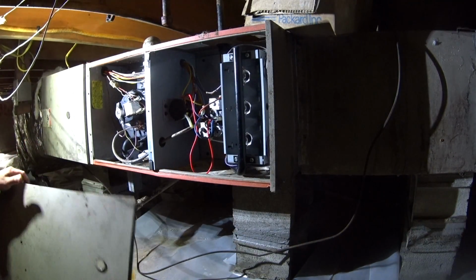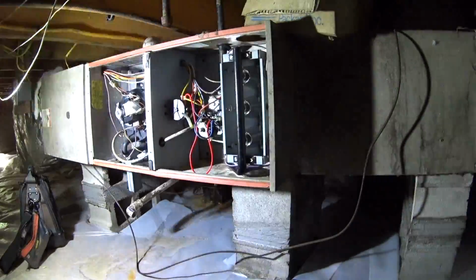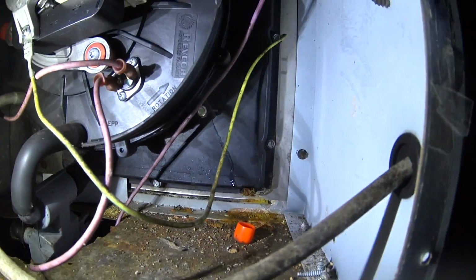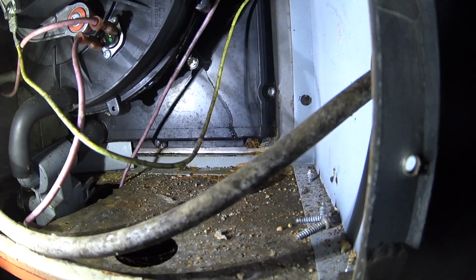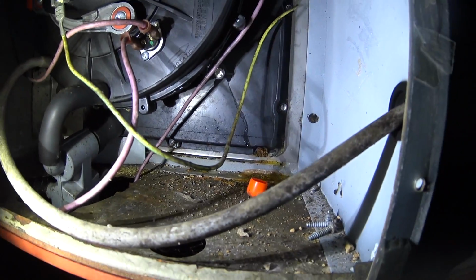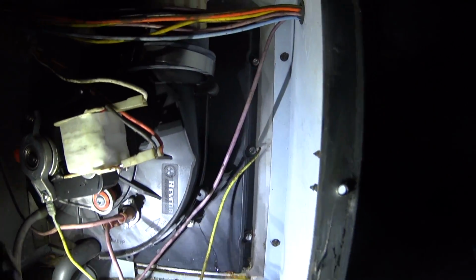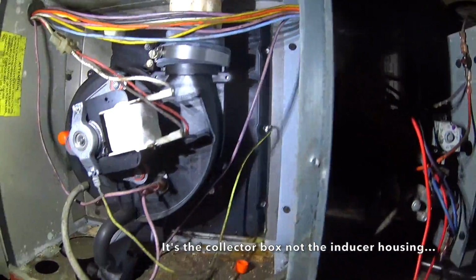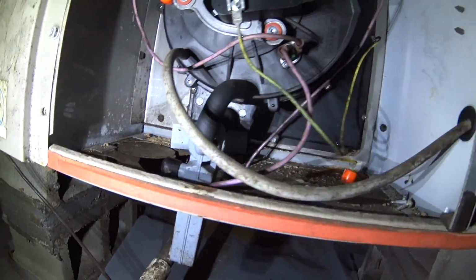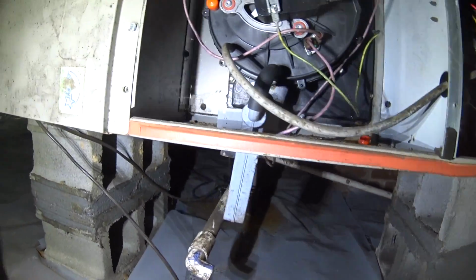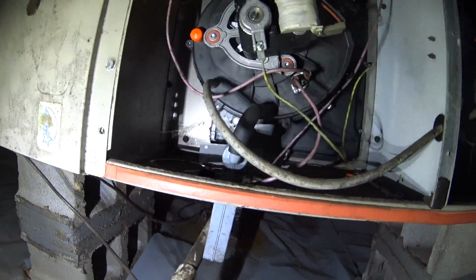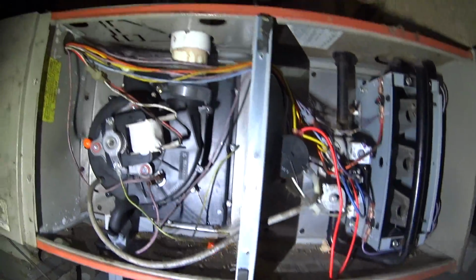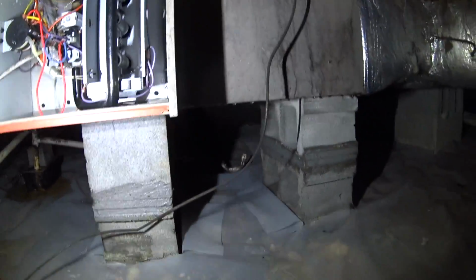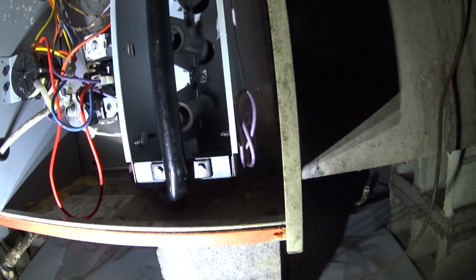Remember that I do. We've got a crack in the inducer housing, which is actually leaking water. Got two cracks in the inducer housing. So, cracks in the inducer housing are obviously not a good thing, but we'll see what the rest of it looks like before we go that far.